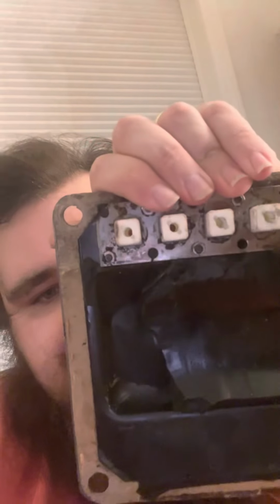When you're doing that, you have to be super careful, because the little metal rods that go through these insulators are very easily ripped off the actual wires that go to the taps on the transformer. Each one of these insulators is keyed on the back, and that key is for slipping those little rods through, making sure they're held in place while a little nut is put on the front to keep it secure.